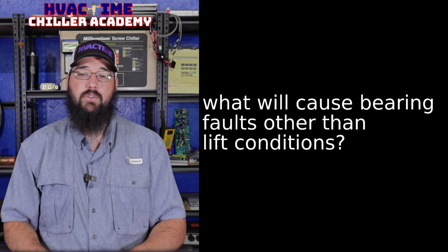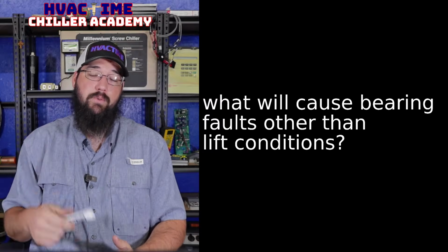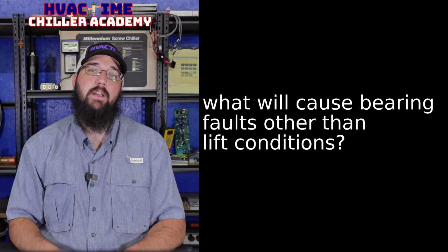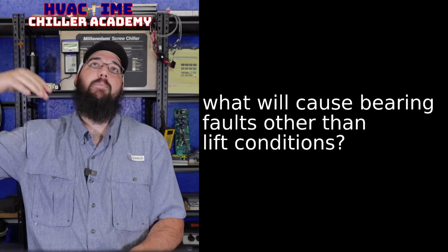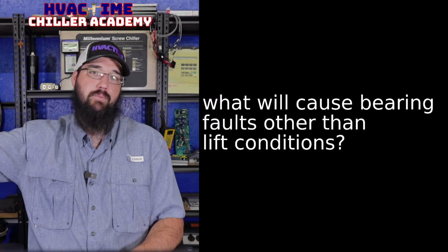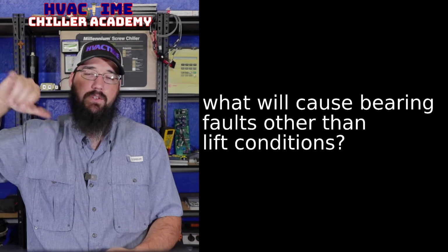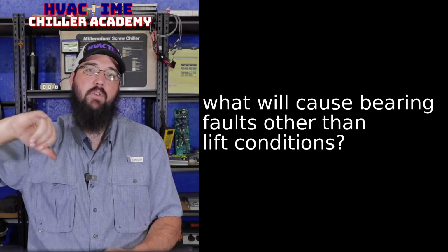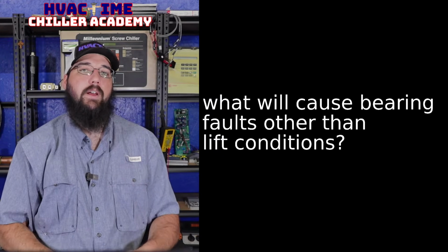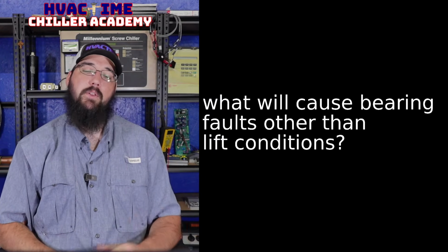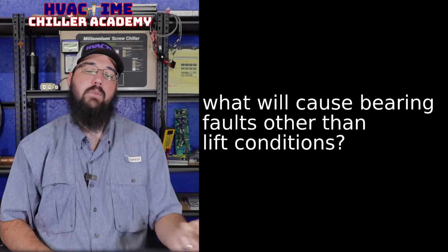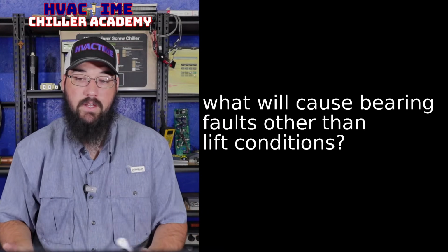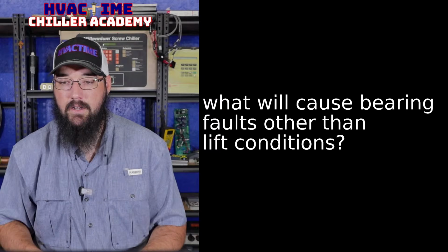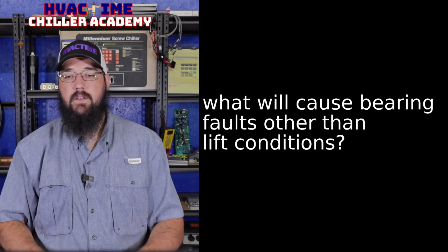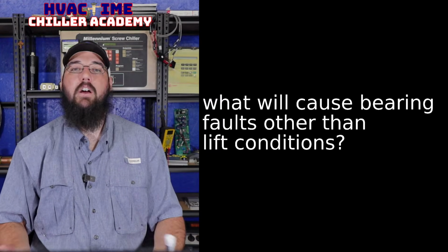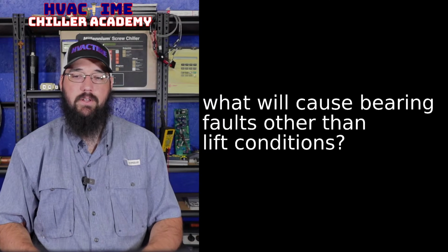And if that suction superheat is still high and your discharge superheat is high, so those are the things we want to be paying attention to. You've still got adequate discharge and suction superheat. If you're seeing those drop, so you're seeing low superheats, you're running a wet suction, period, whether it be from the economizer side or from the evaporator side, saying you have an economizer installed with this compressor.